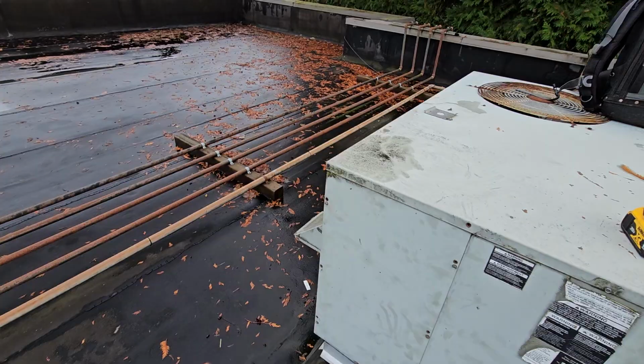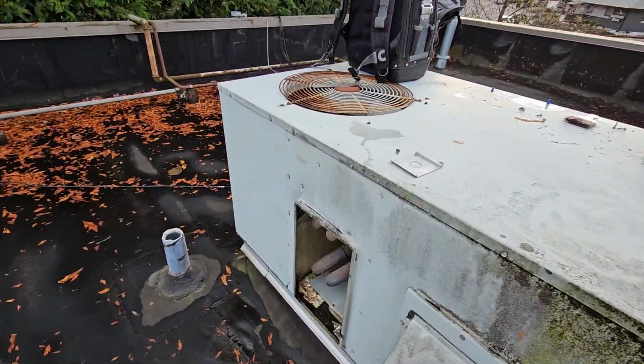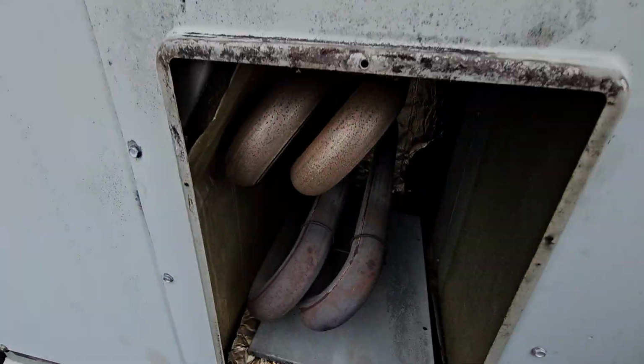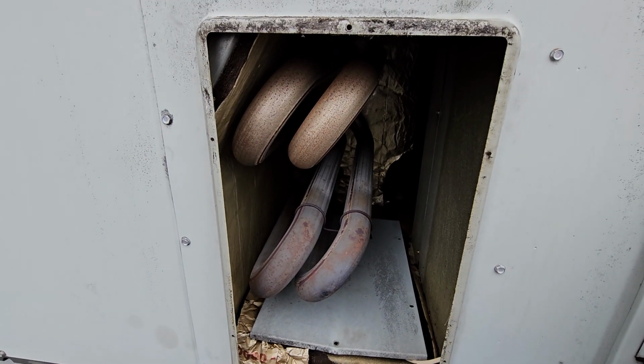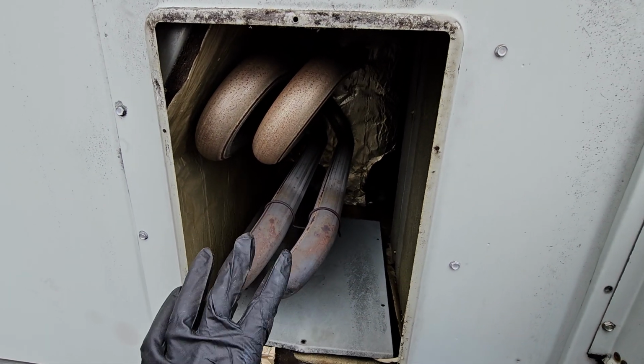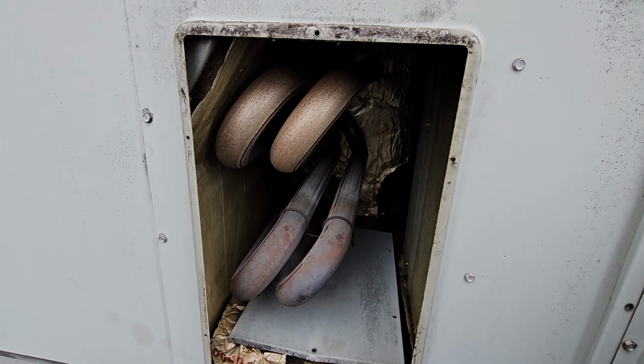So I was a little leery, but figured I'd test everything and go through it. Started off by inspecting the heat exchanger. I've seen people decommission the gas if there's a crack in a heat exchanger or something like that. So I inspected everything on this heat exchanger, and I don't see any cracks or anything like that.